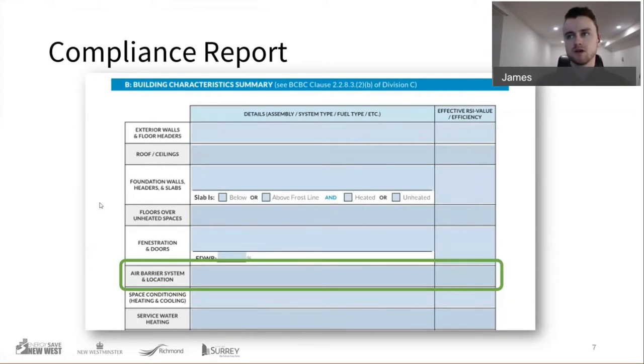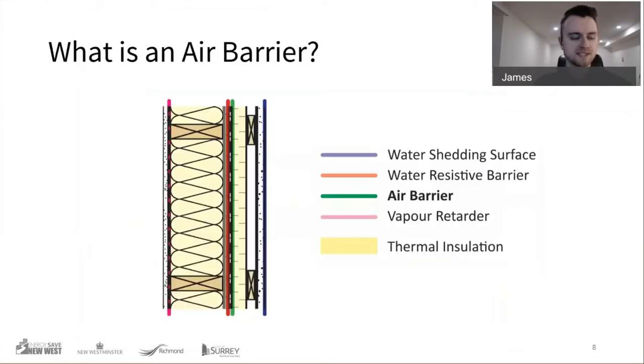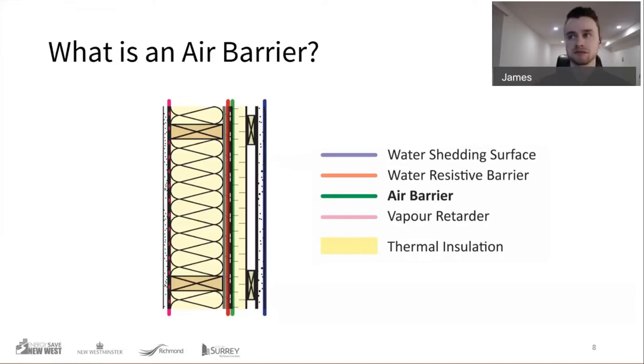Here's a wall example — a simple section of a wall with some exterior insulation. The air barrier is the layer that controls the airflow, and there are quite a few options for what that material or system can be. It's not necessarily the interior polyethylene that most of us are used to. It could be an exterior synthetic sheathing membrane that's airtight, rigid airtight insulation, wood, or other approaches.